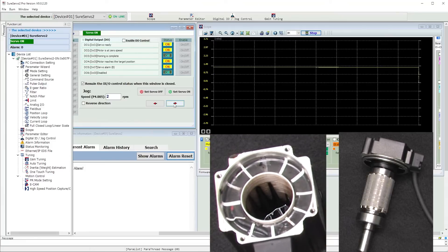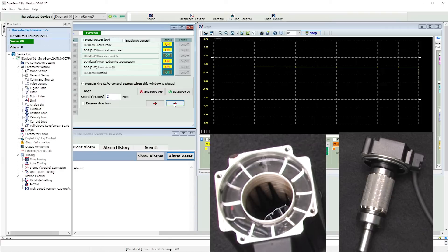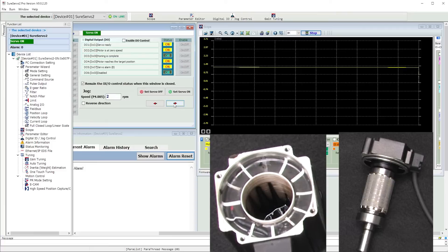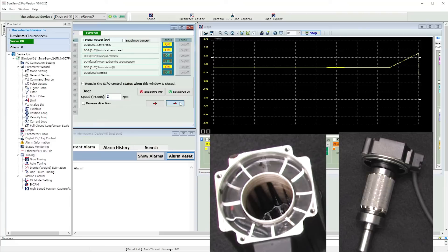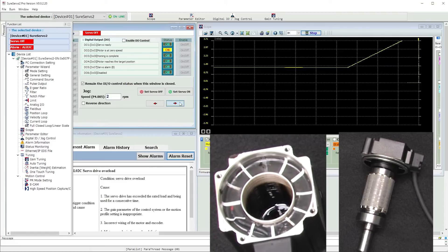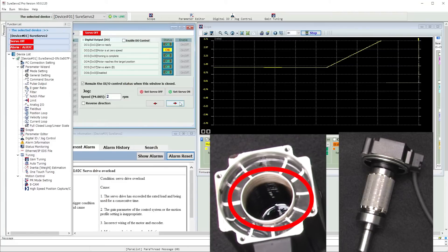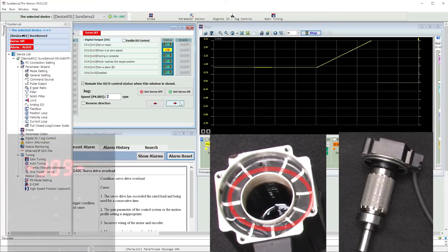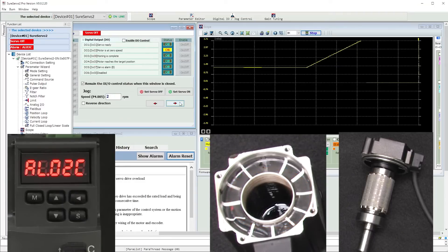The magnetic field is staying there because there is no rotor in the stator to react to the magnetic fields and move the encoder. The drive is going to keep pushing until it gets what it wants or it faults out. If I press jog to increase the current even more, then eventually the drive faults out. The current drops to zero and the magnetic fields go away. And the drive gave us an overcurrent fault.